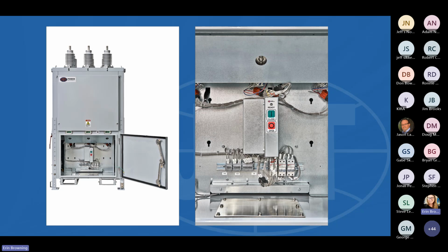Otherwise, there's not really a lot that the customers can do with a control board if it's faulty. This is a device that's easily swappable with a new one. So this is basically the one spare component that we recommend customers keep on their shelves. It's a very quick replacement. And then, for example, if the capacitor fails prematurely, which is a really big concern to a lot of customers, the health of the capacitor, our recommendation would be to keep an entire assembly on the shelf. If there's an issue, they can replace the assembly in the breaker, take the bad one back to their shop and replace the capacitor in their shop, and then put that whole assembly on the shelf for next time. So it's a really easy cycle to swap out spare parts.